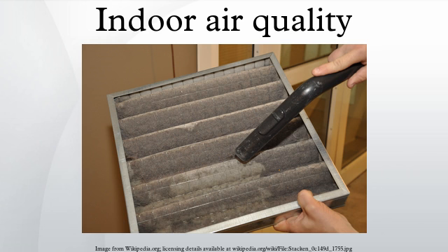However, high humidity outdoors creates the need for careful attention to humidity levels indoors. High humidities give rise to mold growth, and moisture indoors is associated with a higher prevalence of occupant respiratory problems. The dew point temperature is an absolute measure of the moisture in air. Some facilities are being designed with design dew points in the lower 50s degrees Fahrenheit, and some in the upper and lower 40s. Some facilities are being designed using desiccant wheels with a gas-fired heater to dry out the wheel enough to get the required dew points. On those systems, after the moisture is removed from the makeup air, a cooling coil is used to lower the temperature to the desired level.